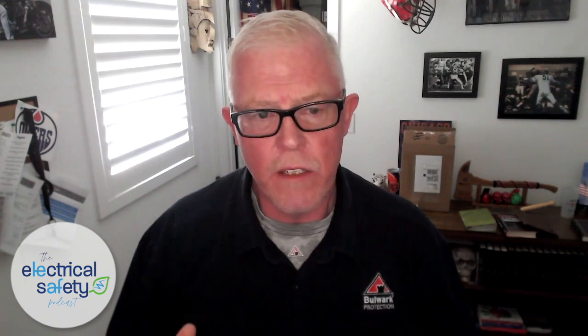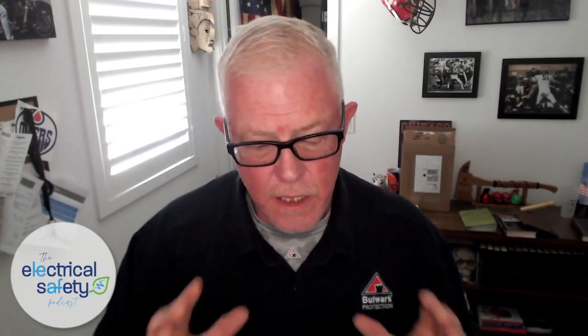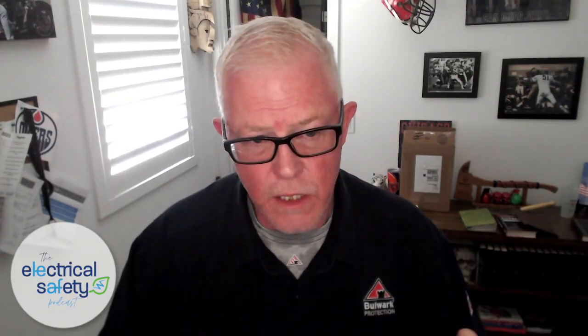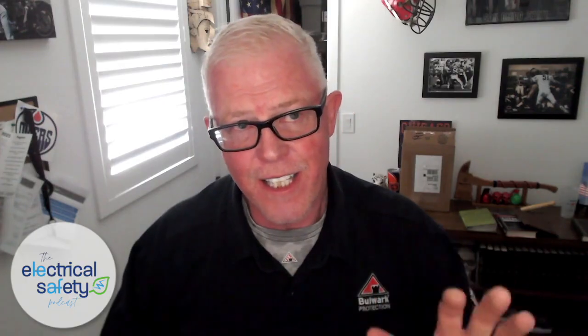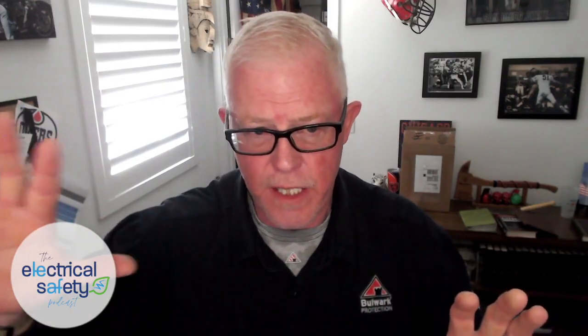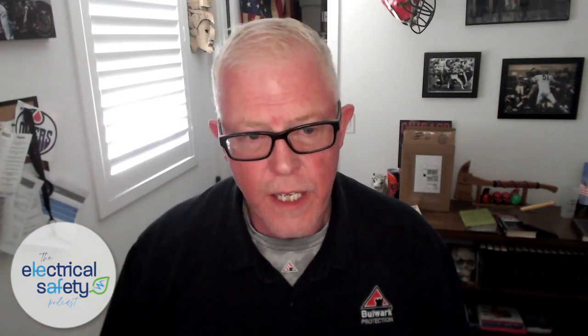You very rarely get the exact incident energy at the exact distance with the exact closing time in an arc flash. So the good news is, wearing your arc-rated clothing, even if it's technically less than the presented incident energy, one thing happens: you will still self-extinguish. You will not ignite and continue to burn.